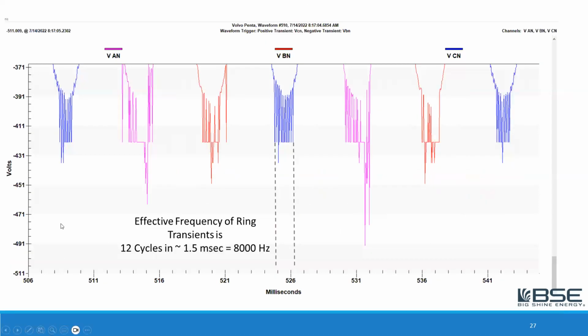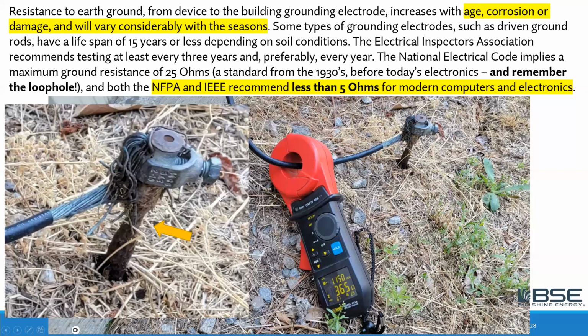This is also another view to give you an idea of ring transients. That's a very rapid ringing or oscillation. Here you can see that there were 12 cycles of up and down for the phase C to neutral voltage occurring in 1.5 milliseconds. That gives you an effective frequency of 8,000 hertz. But the control circuits in a lot of our equipment are designed for 60 hertz power. So you can see it becomes hard to control and regulate, and it's hard to protect against these spikes that you see. Now, one of the problems that we have is that soil conditions and age and corrosion all take their toll on our grounding systems.